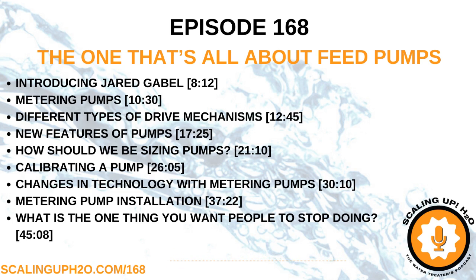And again, talking about smarter technologies, pumps that are able to automatically adapt to fluctuating back pressure are even more hands-off when it comes to calibrating. You don't really have to calibrate pumps that can sense the system around them. When you put in your target feed rate, it's just going to go to the speed it needs to be based on the pressure that it's sensing. So you can make it as complex as you want today, or as simple as you want, depending on the technologies you choose when it comes to calibration.